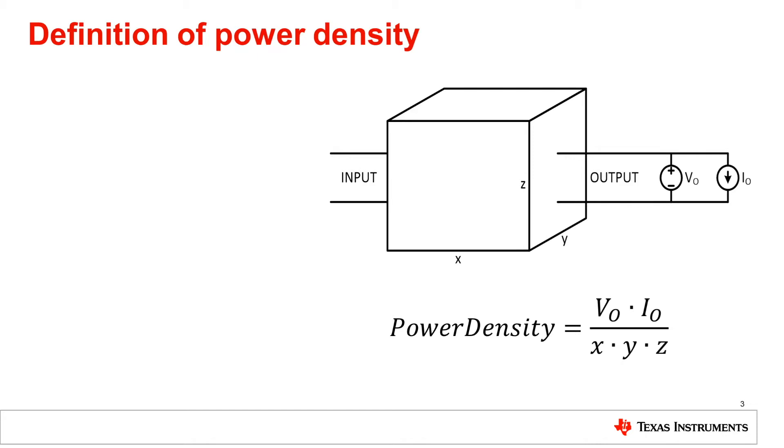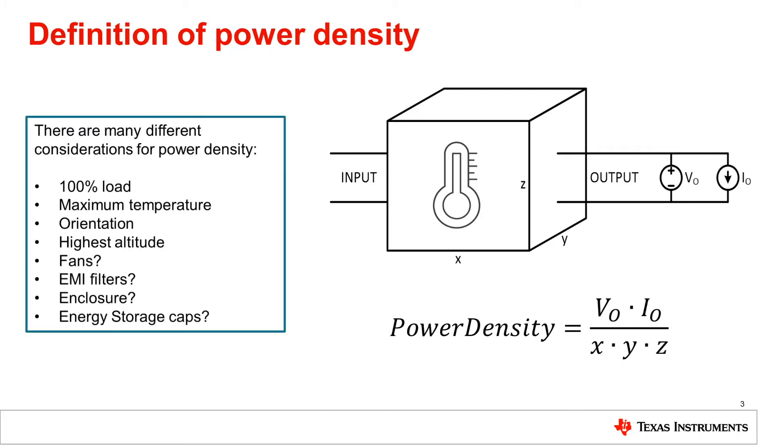The output power in this case corresponds to the continuous output power the unit can deliver under worst-case environmental conditions. The relevant power capability may be affected by the combination of ambient temperature, maximum acceptable case temperature, orientation, altitude, and expected lifetime.